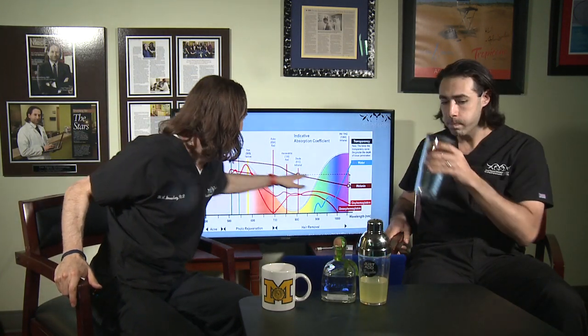This overlays the absorption spectrum for hemoglobin in blood — whether it has oxygen on it or doesn't, the absorption spectra are slightly different. Melanin is pretty stable across the absorption spectrum with a few distinctions, and then water. Knowing what molecules absorb differently at different wavelengths of light, you can pick different lasers to treat different things. Going back to complementary colors: if you want to target something red, you want a green or yellow laser because those will be complementary. The first medical laser developed was a pulsed dye laser — a yellow laser that excellently targets hemoglobin at its high peak.